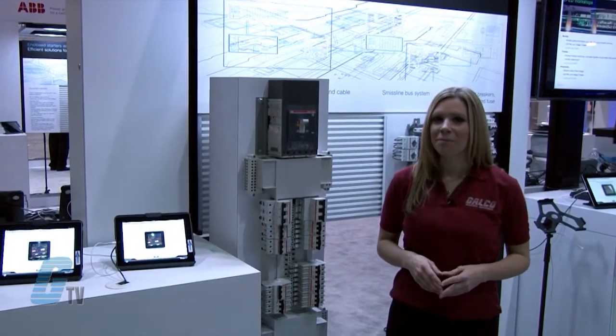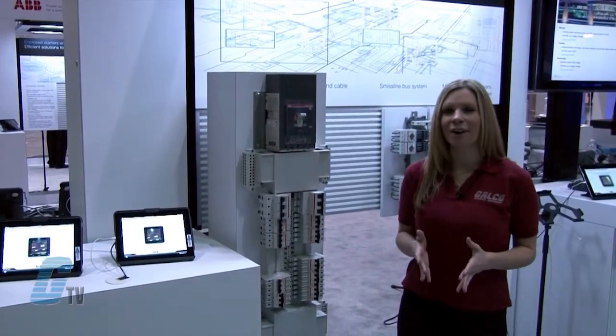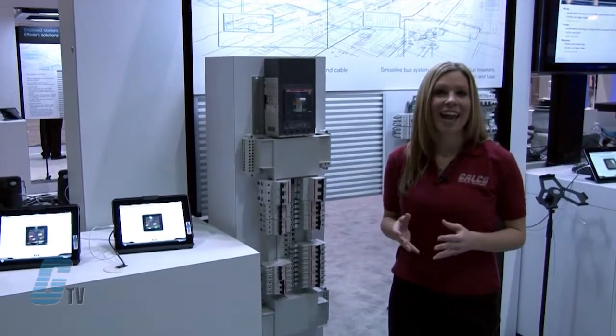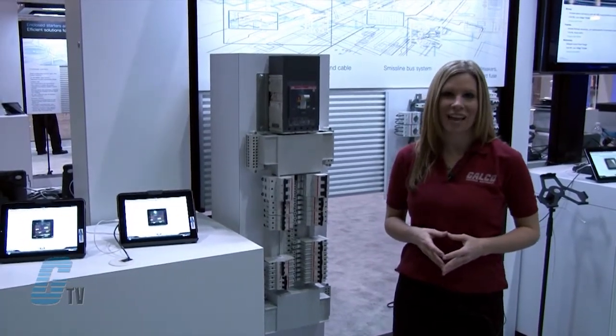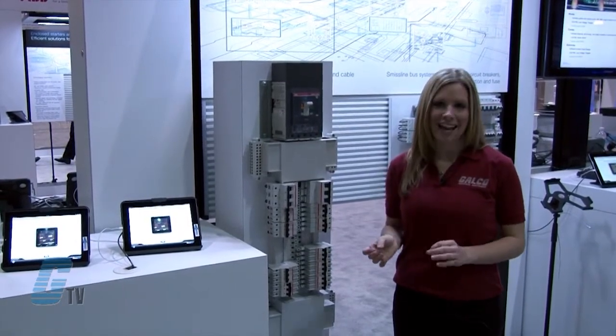The panel board is rated up to 240 volts and 277/480Y volts AC. They have a 35 kA interrupting capacity at 240 volts and 14 kA interrupting capacity at 277/480 volts.